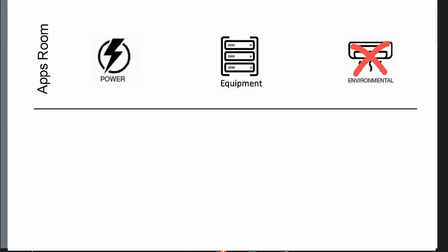It's failed. But these are unmanned rooms. These are just server rooms or apparatus rooms. People aren't there all the time necessarily. So then what happens is that room starts to heat up. It's got lots of equipment with lots of processing power, churning away and getting hotter and hotter. And ultimately, that results in loss of signal.